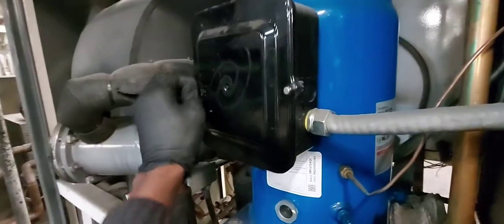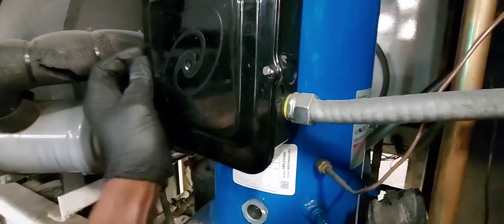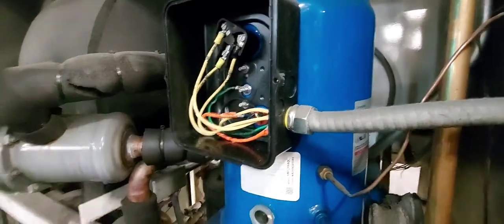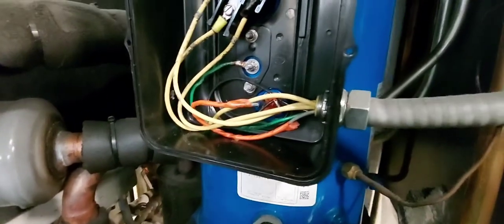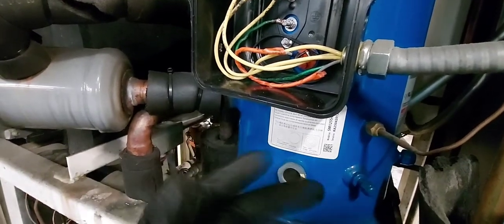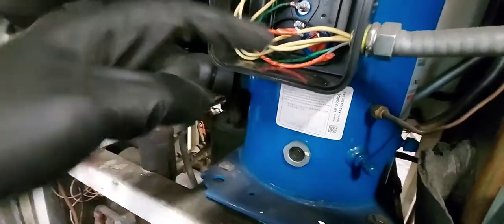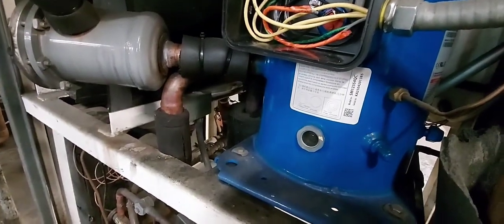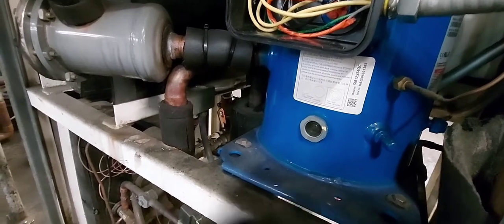This is the HVAC AC unit compressor. The compressor passed the megger test — all the windings checked out, it's electrically sound. I'll leave a link in the description to the video of me doing the megger test.